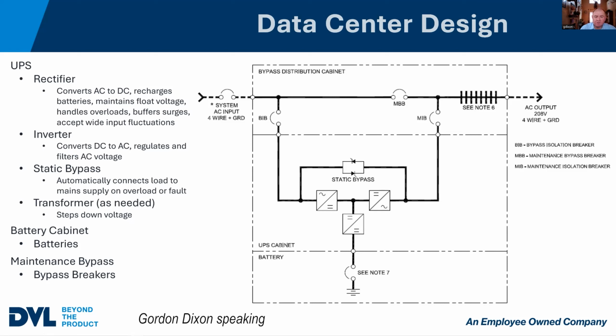In the meantime, the rectifier also helps mitigate buffers from surges, spikes, small brownouts, things like that, so it's cleaning the power up a little bit as it goes through. The inverter, on the other hand, goes from DC to AC, and again that regulates it, so it's just a final check to make sure the power's clean as it's coming through. There's a bypass inside, and I want to be clear on this because there's a difference between a static bypass and a maintenance bypass, and you'll see at the bottom of the sheet there's a maintenance bypass listed. The static bypass inside the UPS is essentially a safety for the UPS itself.